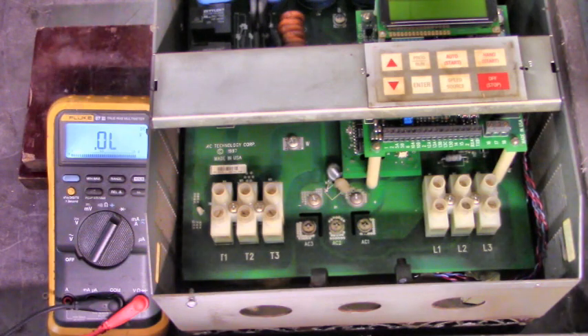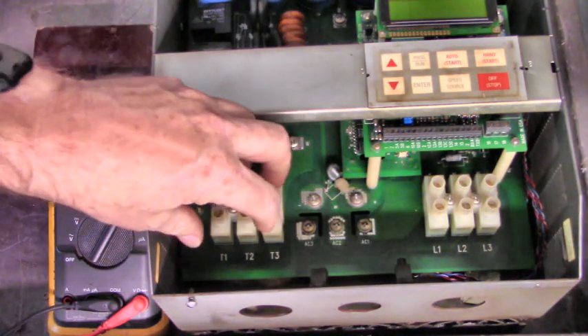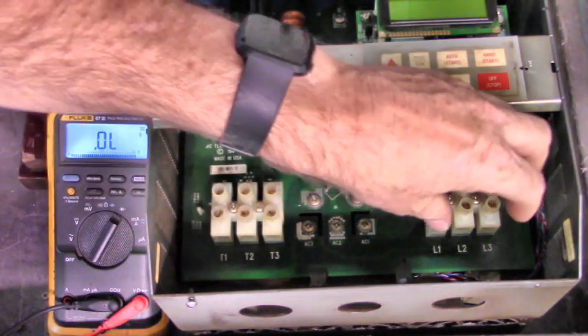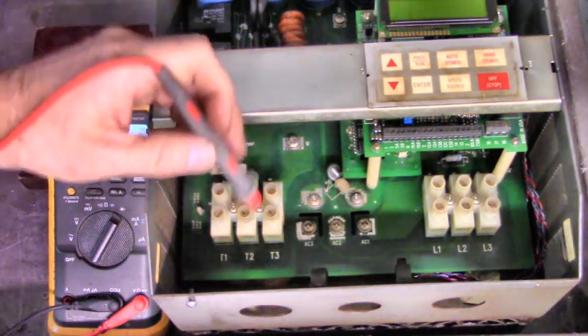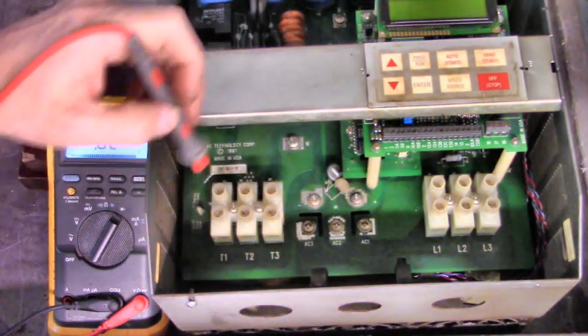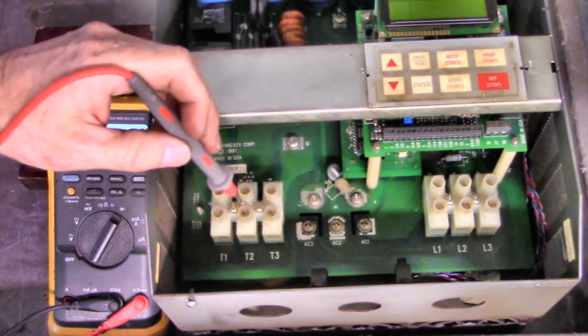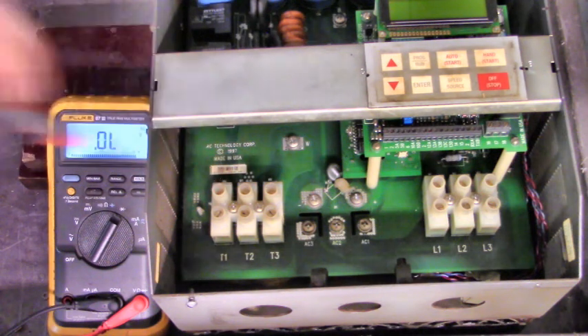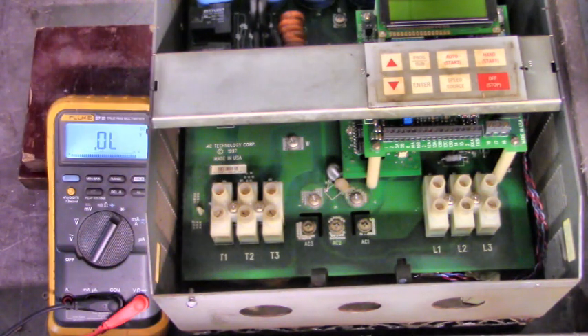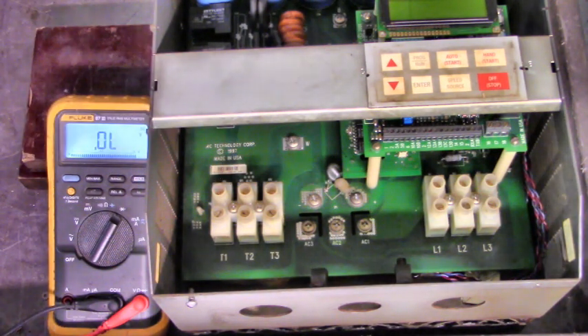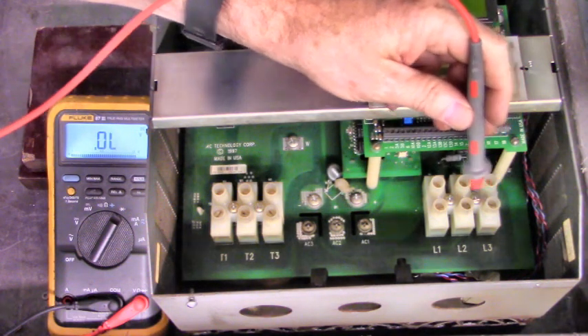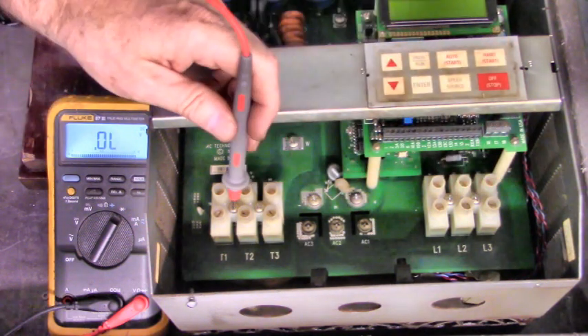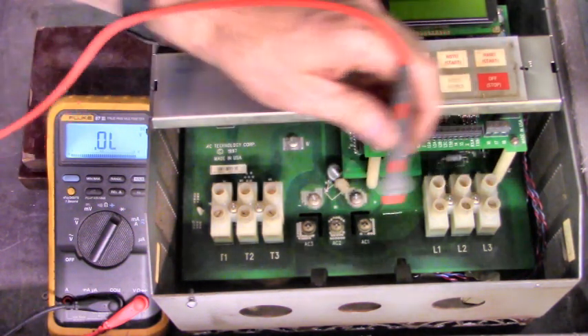Most drives, the line is on the right side and the motor's on the left side. Don't hook this up backwards. You don't want to get the line applied to the IGBT. It will destroy this drive. So, line motor, three-phase bridge in the middle.